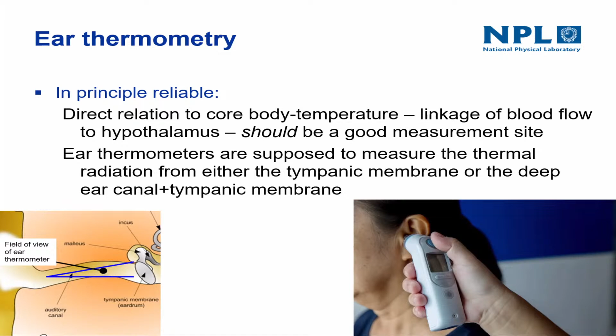When they're made, there's a clinical standard which says their accuracy should be plus or minus 0.3, in some regions even plus or minus 0.2, in the normal range of use. You have to keep in mind that, when they're used regularly in hospital or clinical environments, that uncertainty will grow. They're not perfect devices, not like liquid-in-glass thermometers, which would continue to work reliably year after year until they broke. These devices need periodic checking to make sure they continue to work reliably, and they need to be checked against traceable standards. So if the manufacturer gives you or sells you a standard to calibrate your device against, you must make sure that it is traceably calibrated to your national reference.